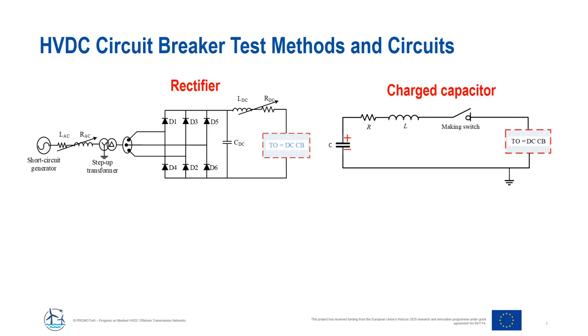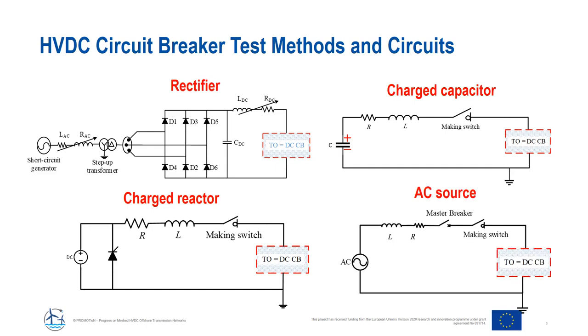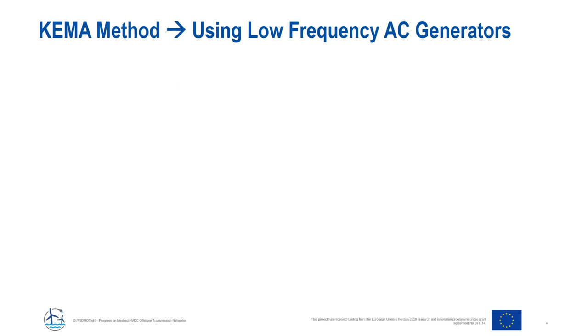Another option is using a charged reactor, where reactors are charged with current to test DC circuit breakers, but this requires high-quality reactors capable of handling large currents. Another commonly used method uses AC sources — short-circuit generators at low power frequency — with the main focus on producing quasi-DC current, which has been used in many HVDC circuit breaker developments. Therefore, at KEMA Labs we took on the challenge of developing a test method that can ensure service-like stresses to the HVDC circuit breaker.